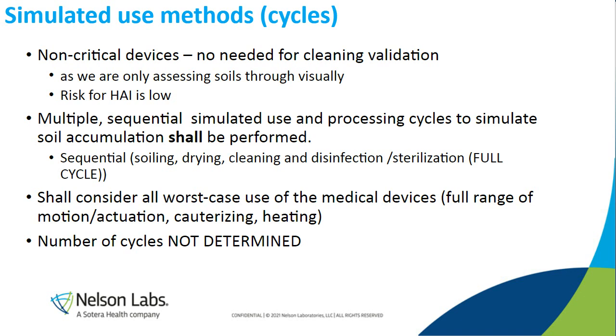Now you might ask, how many cycles do I need to perform? What is a good cycle number? In the previous versions of ST98, we did put a cycle number. However, the committee during the final drafting decided that no, we're going to leave it to interpretation. So the number of cycles is not written down or given a number. However, 6 simulated use cycles has been accepted by regulators and has been used historically for all reusable medical devices since the 2015 guidance document came out. So we would recommend at least 6 simulated use cycles for critical and semi-critical devices before moving on to the cleaning validation.